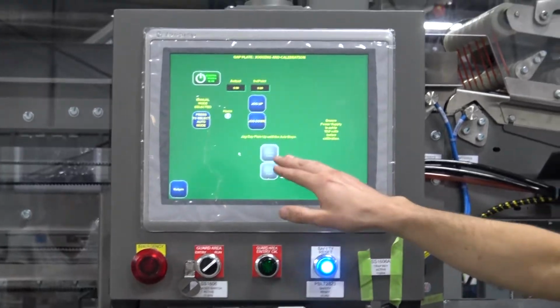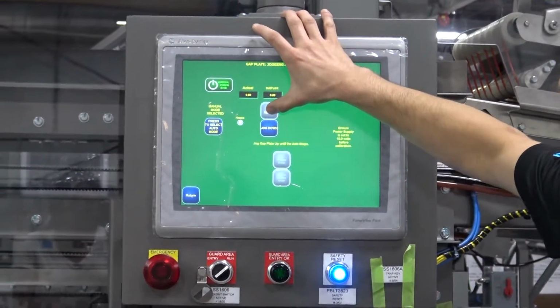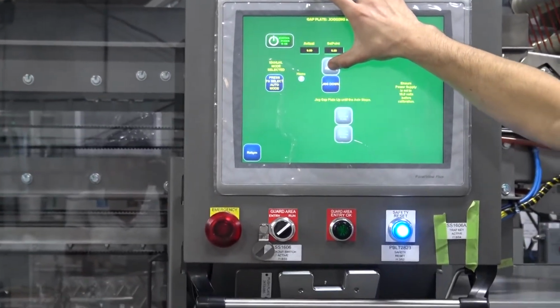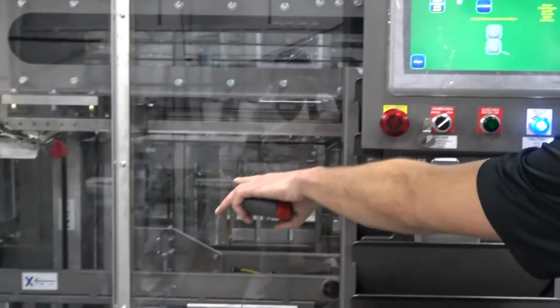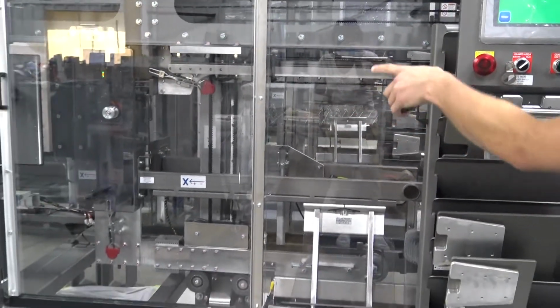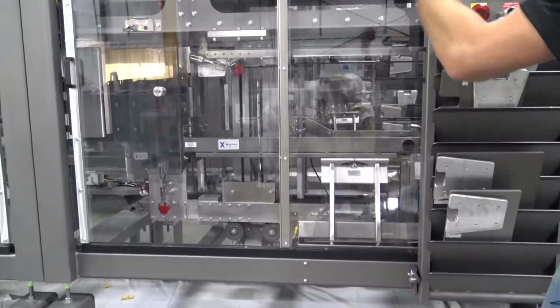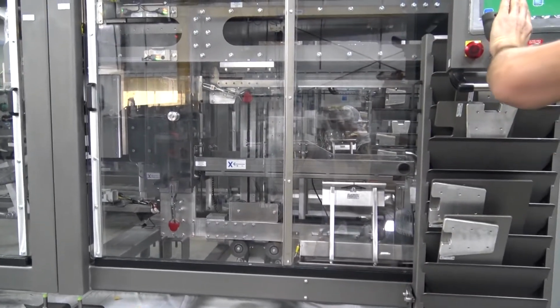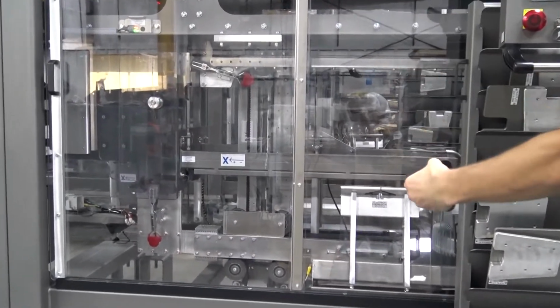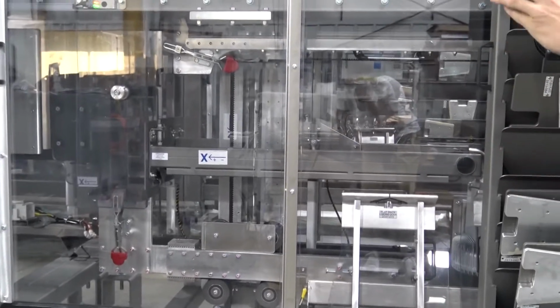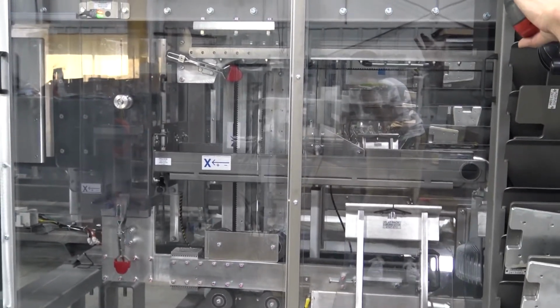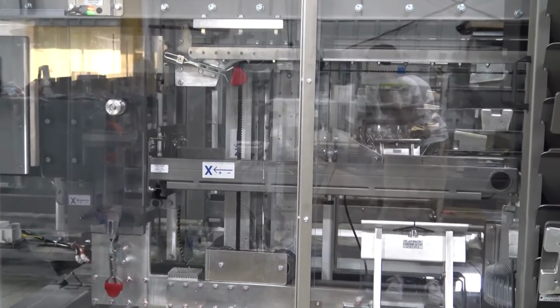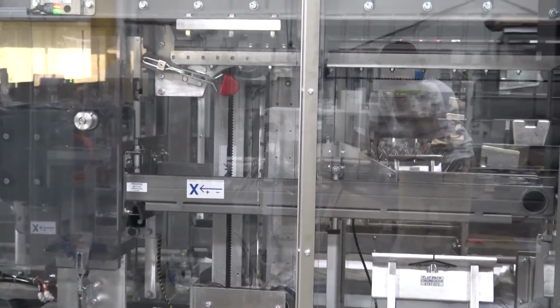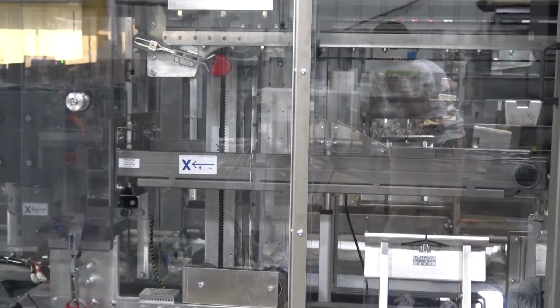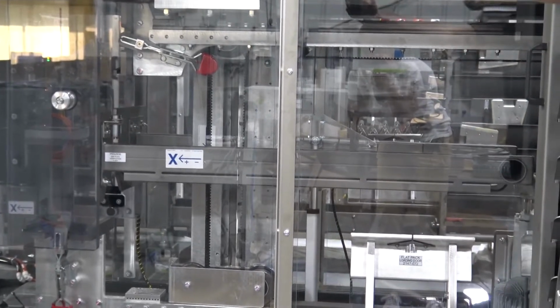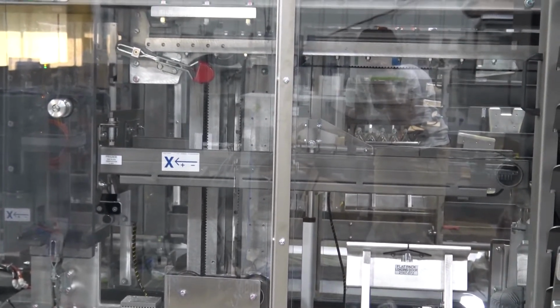Now it's asking you to jog the axis up until it stops. One thing to note: while you're doing this, you'll see the gap plate assembly jogging up, but you also want to make sure your pusher plate assembly isn't pushed out past the point where the gap plate will interfere with it. If the pusher plate is pushed out too far, you'll cause a bind and interference while manually jogging the gap plate up. So make sure the pusher plate is pulled back far enough.